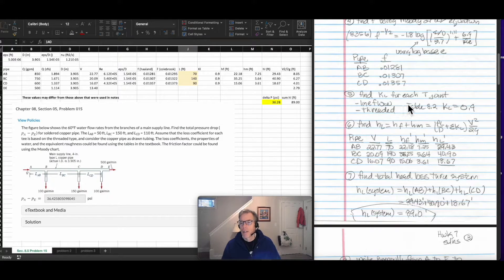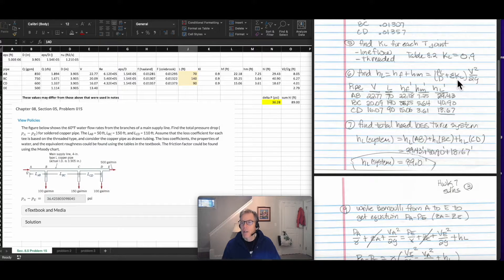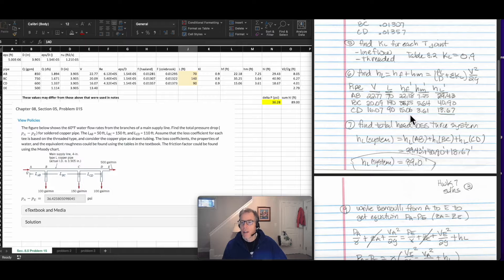Next, I found the minor loss coefficients for each of the T-joints. I looked it up in the table from the textbook. For line flow with threaded connections, the head loss coefficient is 0.9. Now I had all the information needed to calculate the head loss, which is a sum of the friction losses and the minor losses. Using the Darcy-Weisbach equation — F times L over D times V squared over 2G — I got the major friction losses. Adding the minor loss coefficients times the velocity head gave the minor losses, and I got head loss values for each pipe section.